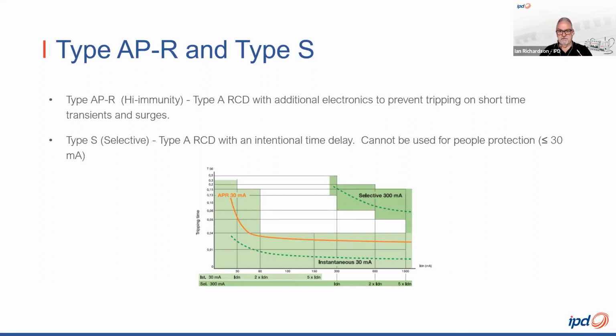Yeah, and the other type available is type S. Type S, or selective RCD, is also based on the type A RCD, but with an intentional time delay built in. As you can see on the graph, the time current characteristic is completely different. We use this in a similar way to discrimination of circuit breakers, which allows us to place an RCD above another RCD in a network.